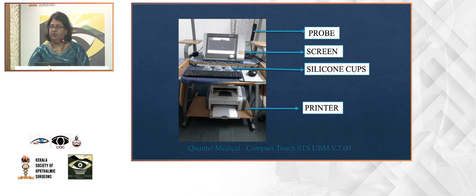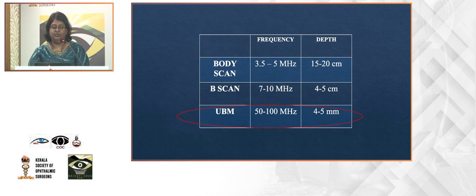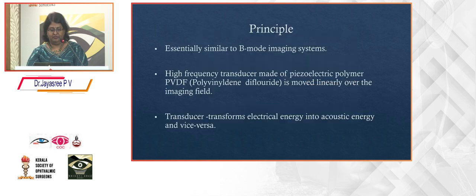This is how the UBM looks. It has a probe, a screen, and it is done with water immersion. It has silicone cups, and between the B scan and the UBM, the frequency is different. UBM has a high frequency compared to a B scan, and hence because of the high frequency, the depth of penetration is just 4 to 5 millimeters, and you are able to image only that much depth. The principle is similar to B scan imaging.